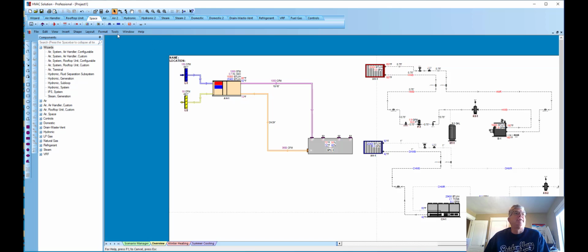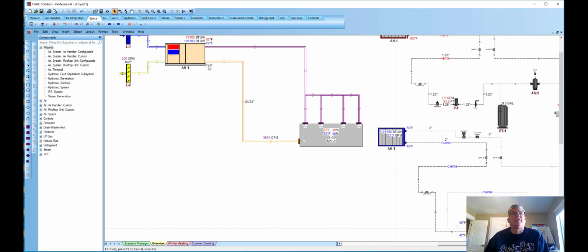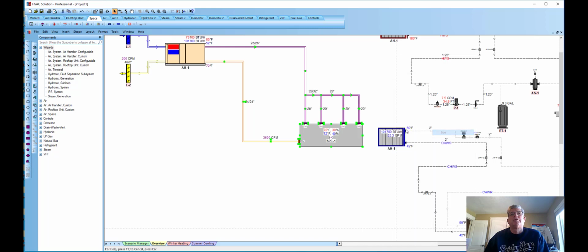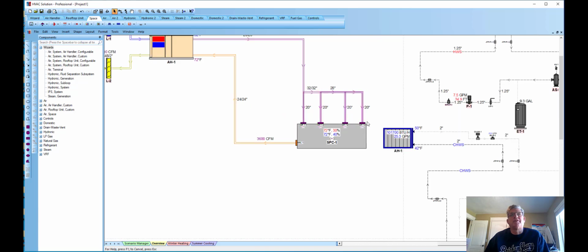You could even show here, as you want to, maybe they're going to all come together like this. Maybe that's how they're all going to be ducted. So then you drag the box across, look at all those duct sizes, and get an idea of what you're dealing with. So each one would be a 20-inch round, 28-inch, and then rectangular. Whenever you see those 3 lines there, that means that's a round.